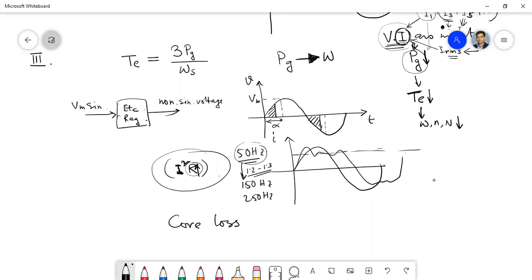It is lost due to the tank of the transformer. In the tank, sometimes eddy current flows. Now, this loss, as here you have high frequency component, generally we neglect that stray load loss because in 50 hertz frequency that eddy current loss in the other non-laminated portion of the transformer will be quite less compared to the major two losses. But here, due to the high frequency component of harmonics, you will have more stray load losses.